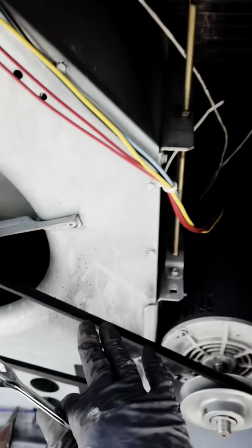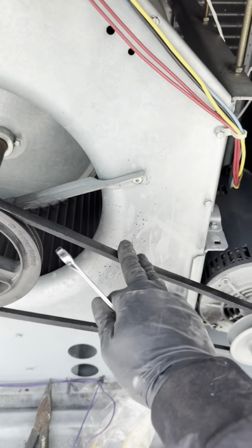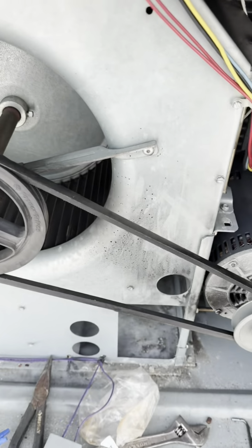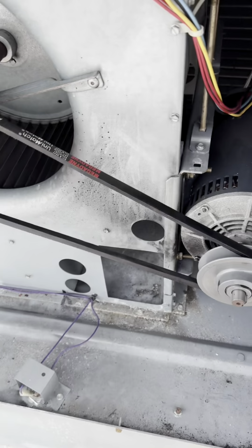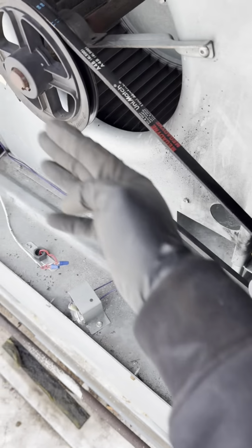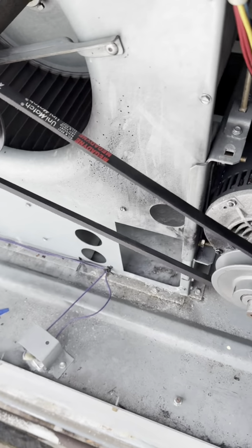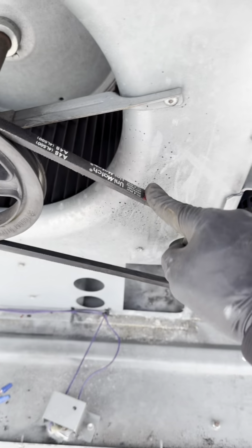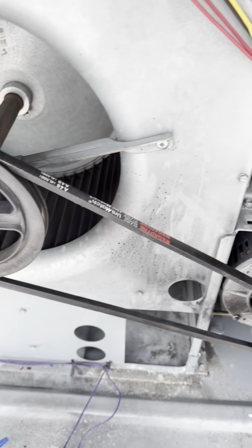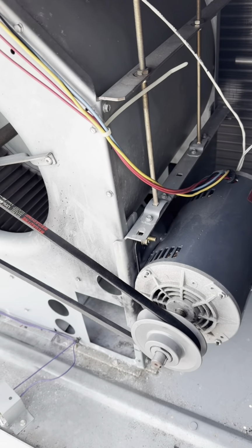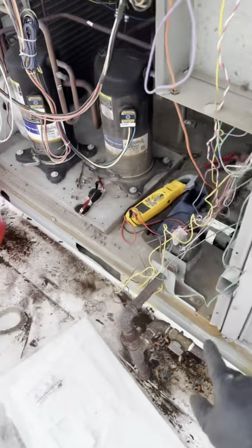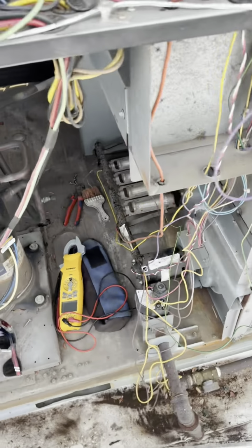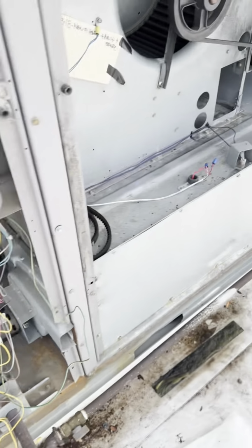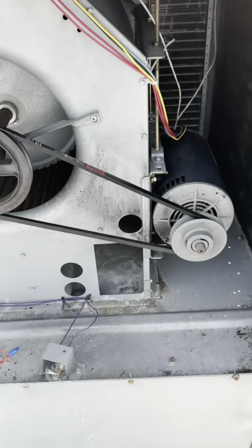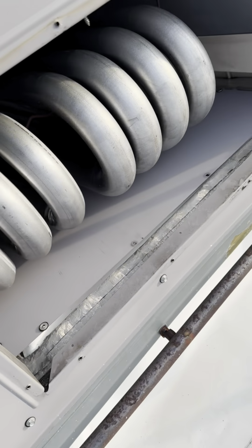And we're gonna go ahead and tighten those up, set the belt tension to about 1 inch of play, and leave it there. We're all set. Put on a new pulley. It's aligned with the blower pulley, and it has about 1 inch of play. Everything's tightened up. I just still have to get some wire ties for this wiring, and we could fire this thing up to smoke out the heat exchanger. All right, everything's buttoned up.